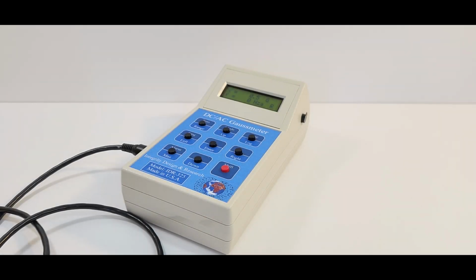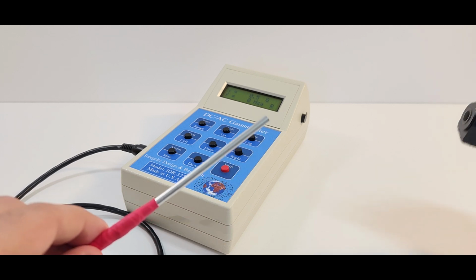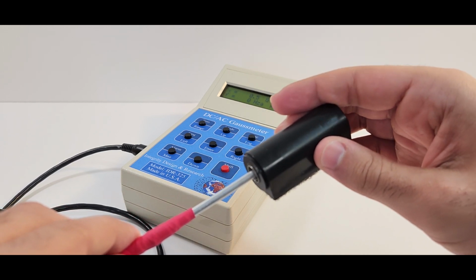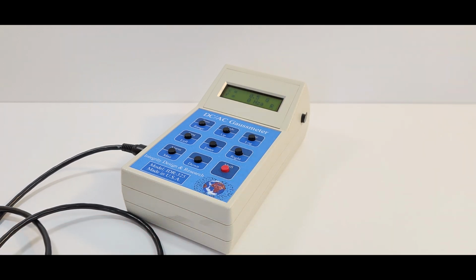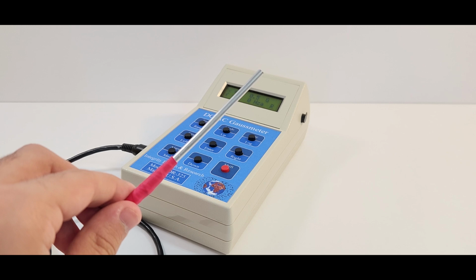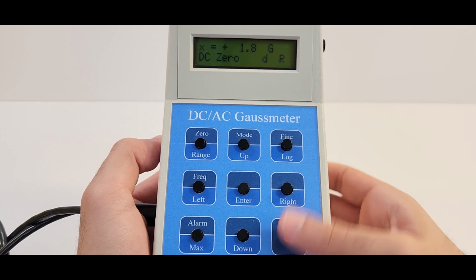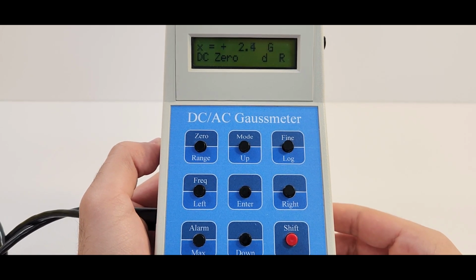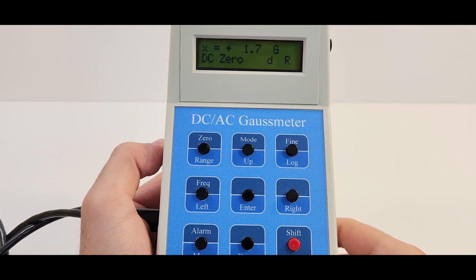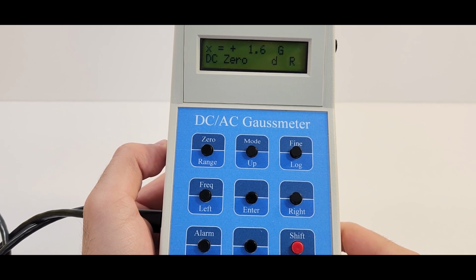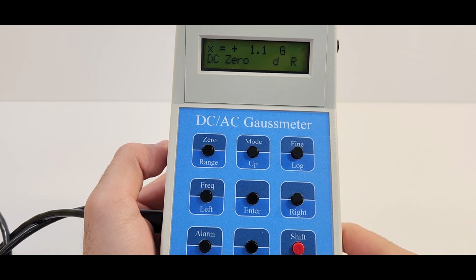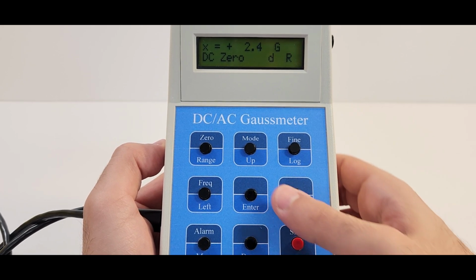Zeroing the meter is generally only needed one time. Rest assured, the meters are shipped zeroed by default. Typically, the recommended zeroing procedure is done by putting the probe inside a zero Gauss chamber, as such. If that's not possible, simply move the probe outside the vicinity of any nearby magnetic fields. To zero the device, press Shift, then Zero. This only needs to be done for DC mode, indicated by the D in the bottom right corner. This can take up to 2 minutes, but typically is far less. Lastly, press up, down, left, right, or enter to exit the automatic zero mode.